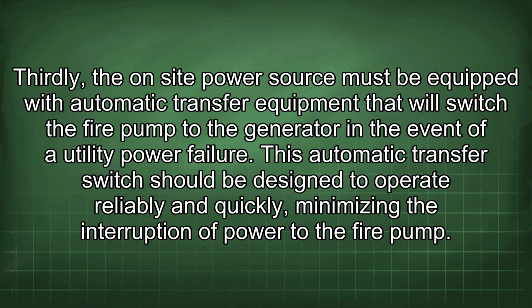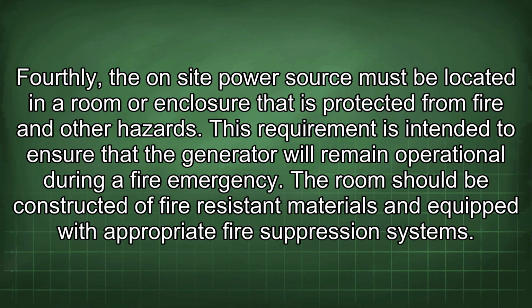Thirdly, the on-site power source must be equipped with automatic transfer equipment that will switch the fire pump to the generator in the event of a utility power failure. This automatic transfer switch should be designed to operate reliably and quickly, minimizing the interruption of power to the fire pump.